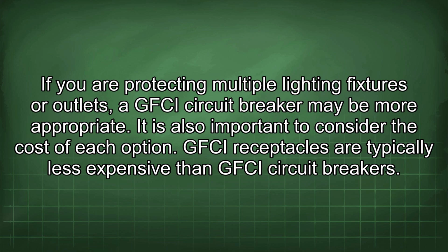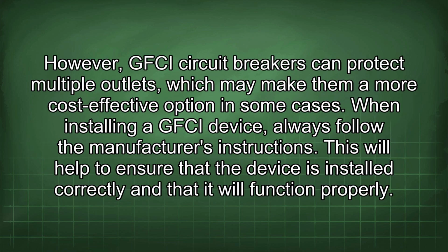It is also important to consider the cost of each option. GFCI receptacles are typically less expensive than GFCI circuit breakers. However, GFCI circuit breakers can protect multiple outlets, which may make them a more cost-effective option in some cases. When installing a GFCI device, always follow the manufacturer's instructions. This will help to ensure that the device is installed correctly and that it will function properly.